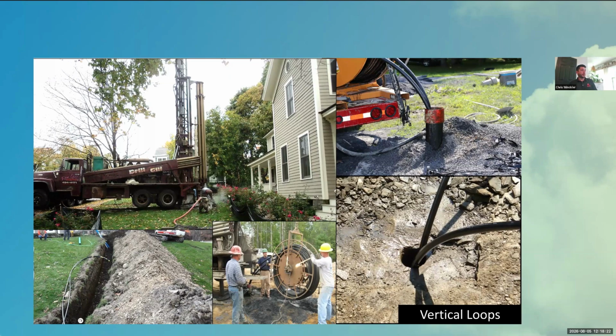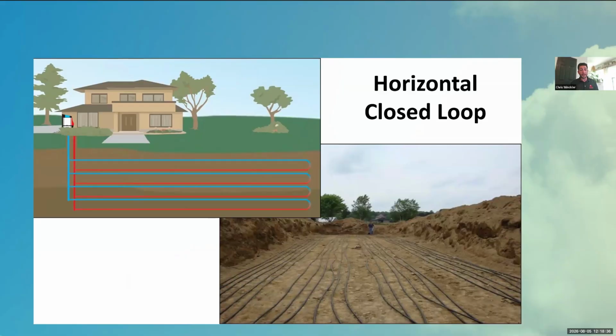So here's one form of ground loop we install, and I'd say nowadays it's the most common. We used to be about 90% horizontal systems and only 10% vertical. Now, mostly for space reasons and because drilling costs are coming down, we almost don't do the horizontal type of system you see on screen—maybe 1 or 2 a year. So it's about 99% vertical, with less than 1% horizontal systems, more for residential, even though we've seen them done in commercial applications.